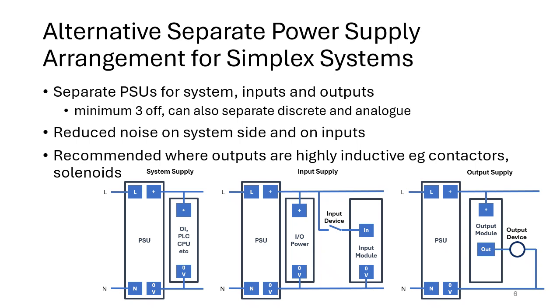There will be one for the system, there will be one for the inputs, and there will be one for the outputs. And if you're really concerned about the analog system, you may even have an additional power supply or power supplies to provide the analog devices, because that makes extra sure that you're having isolation between the inputs and the outputs and both discrete and analogs. If you're doing that, you'd also need to look at the wiring, because you'd need to make sure the analog wiring is maybe segregated from any discrete wiring, certainly from any high power wiring, and you may also look at shielding and earthing in more detail as well. But the key point of doing this is it reduces noise on the system side and from the inputs and the outputs. Definitely recommended where you have outputs which are highly inductive, such as a lot of contactors and solenoids.